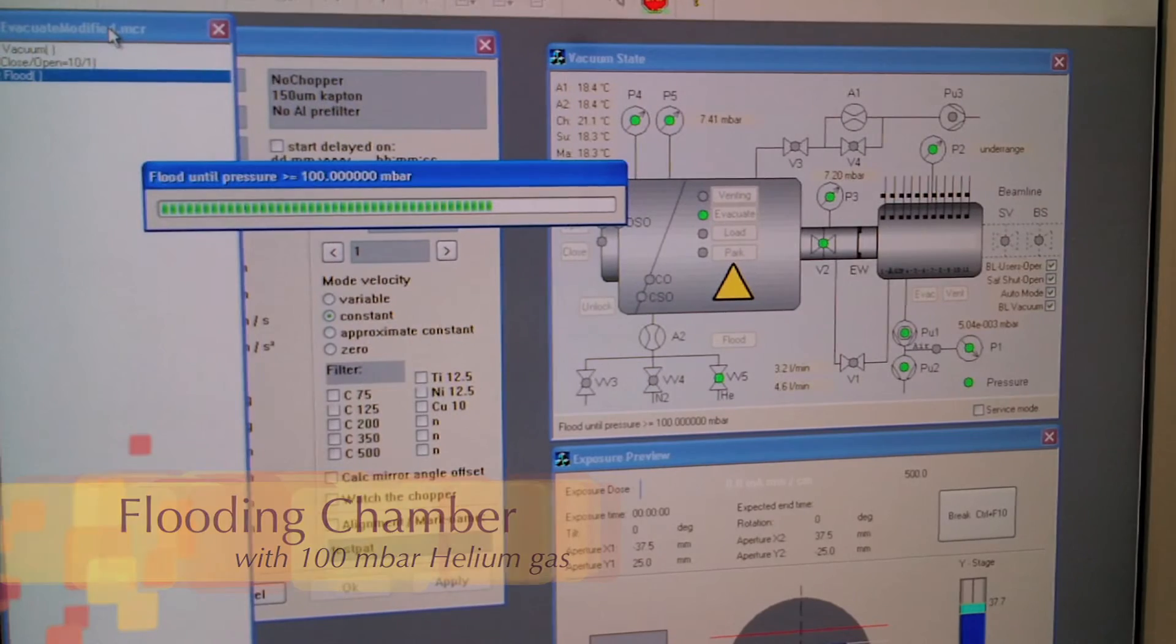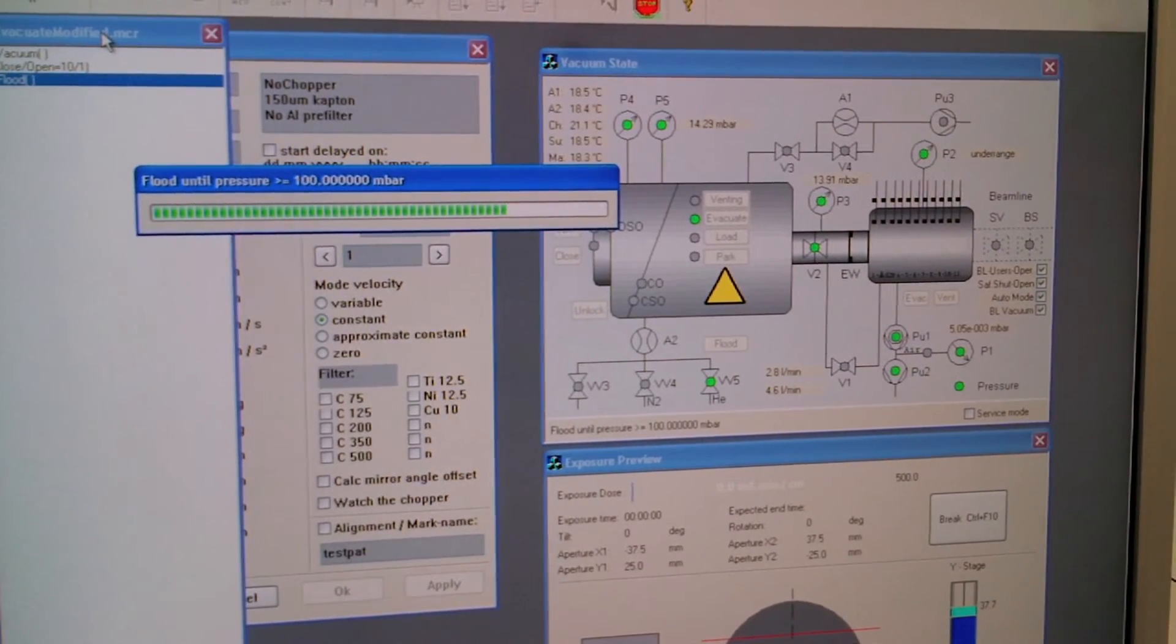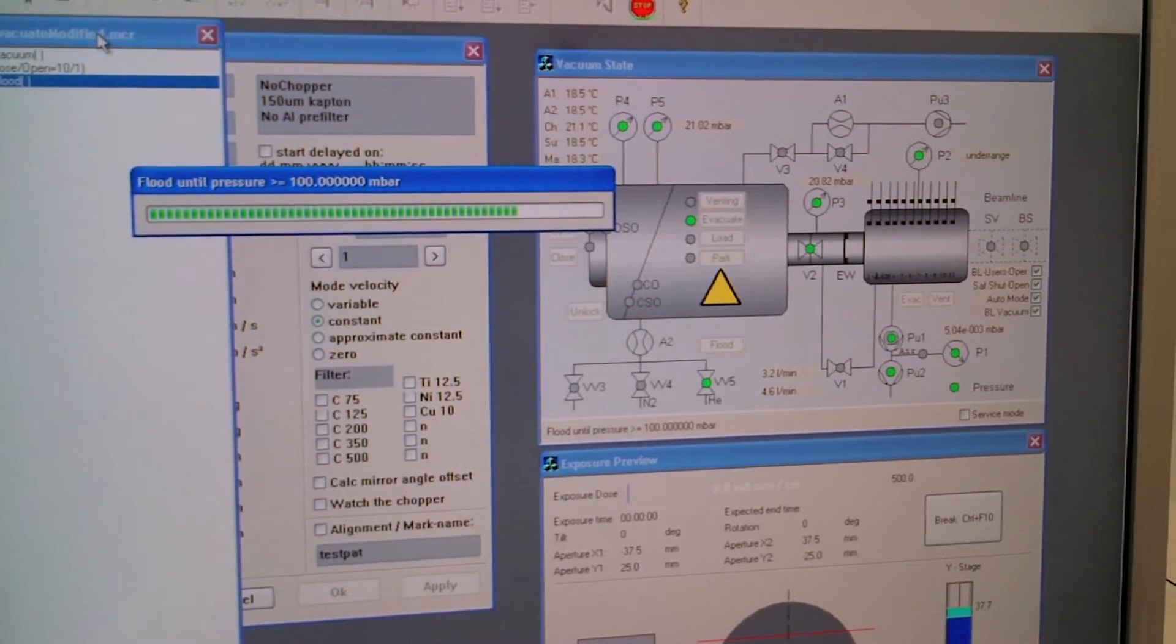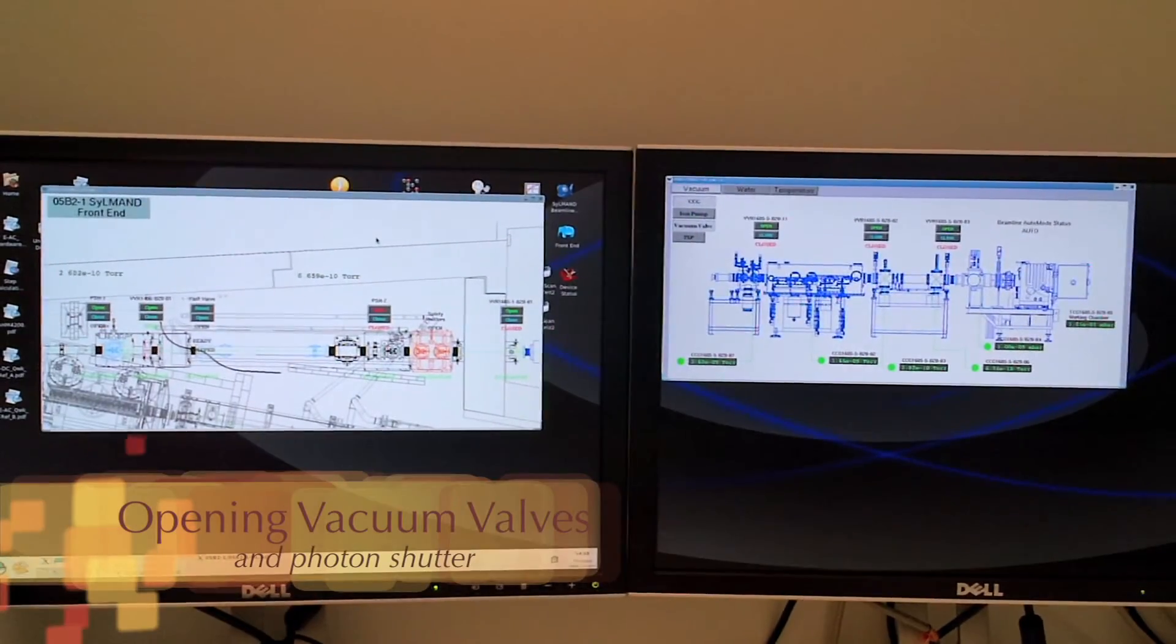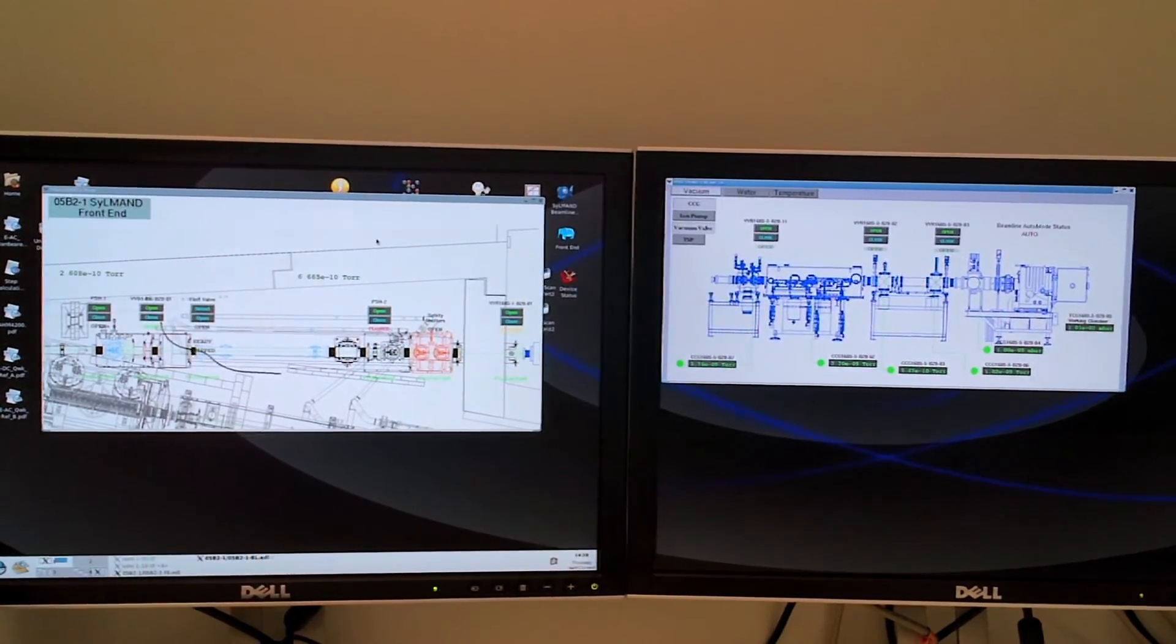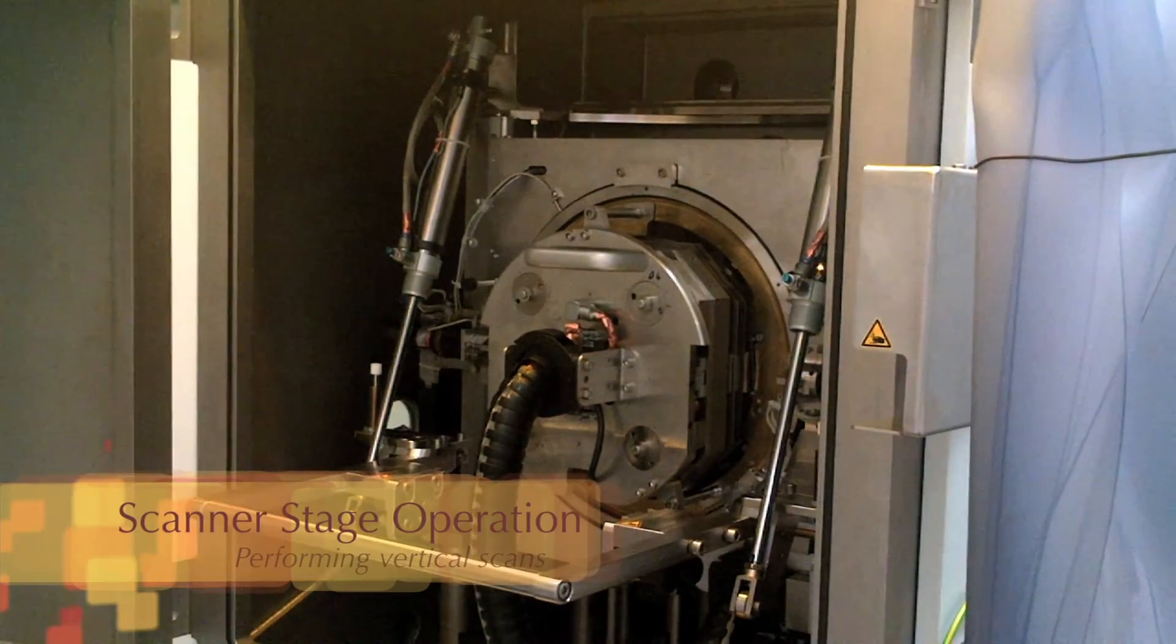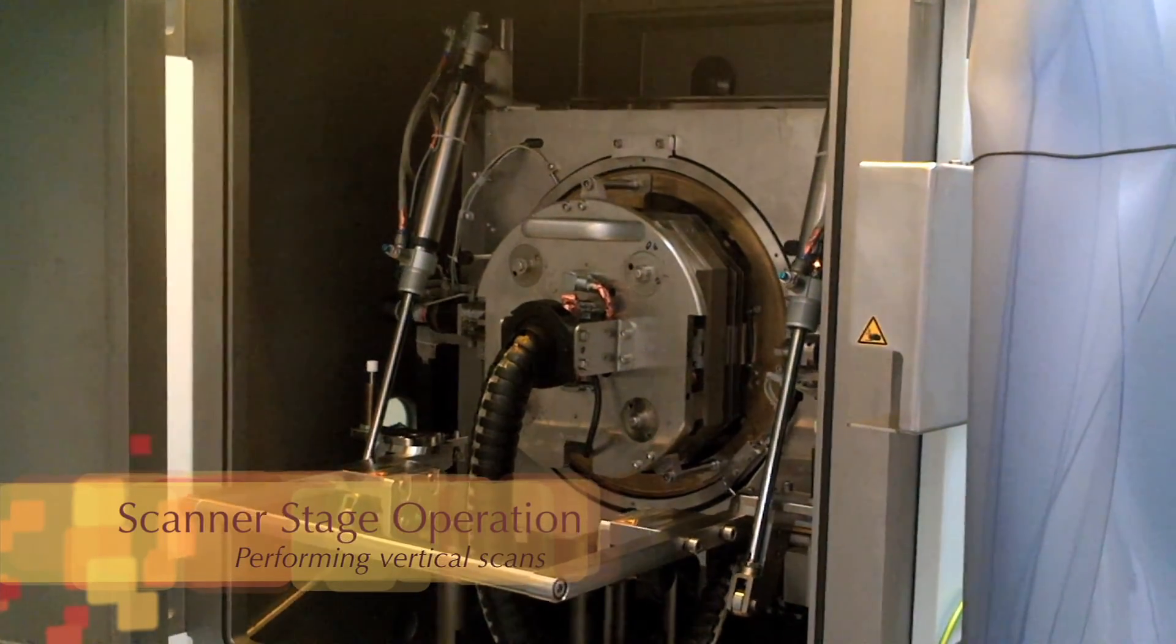The helium environment helps with better transfer of heat away from the sample and the mask to the cooled external chamber walls. The scanner software which handshakes with the beamline controls then starts the exposure by opening the vacuum valves and the photon shutter to let through the X-ray beam to pass onto the sample from the synchrotron ring. The scanner stages scan vertically to integrate the dose through the full height of the exposure scan.